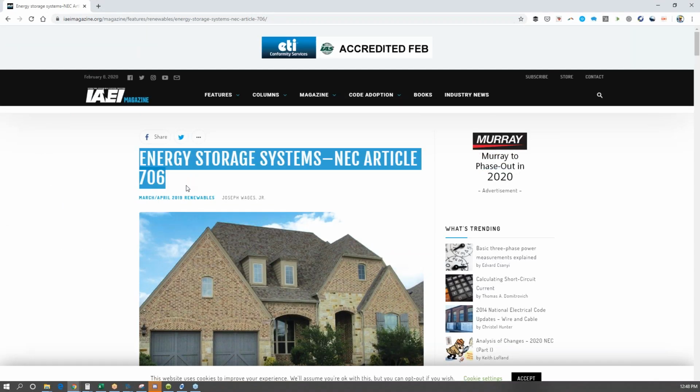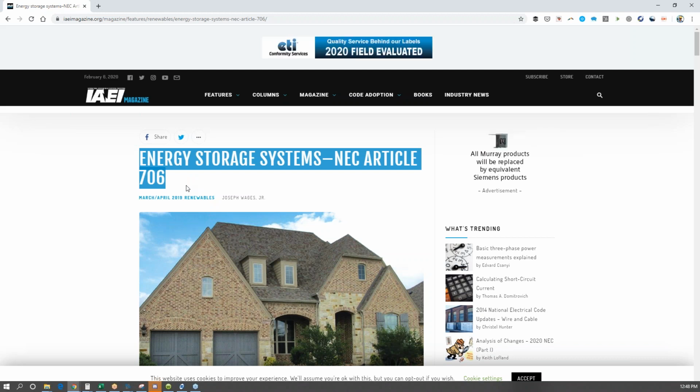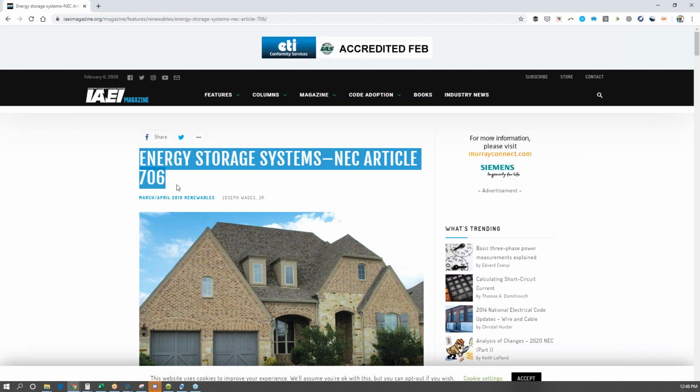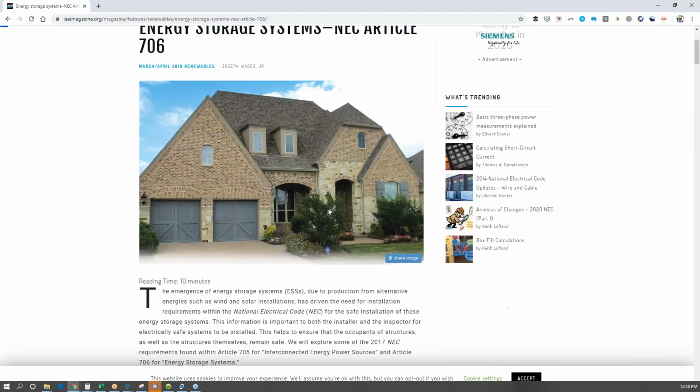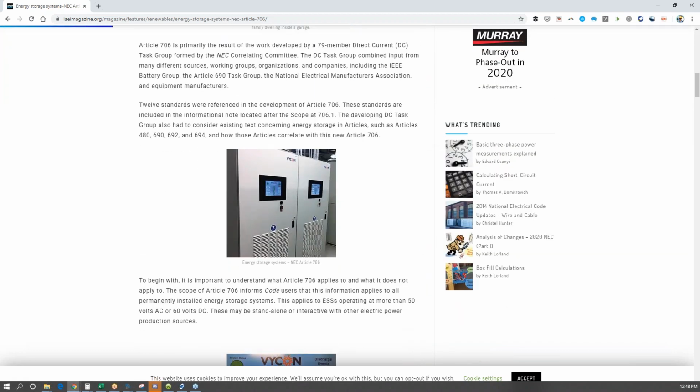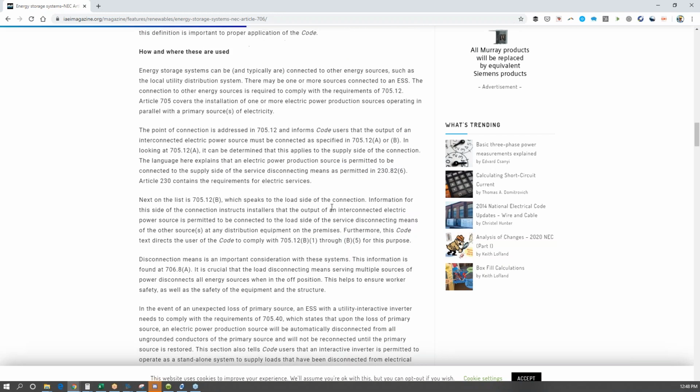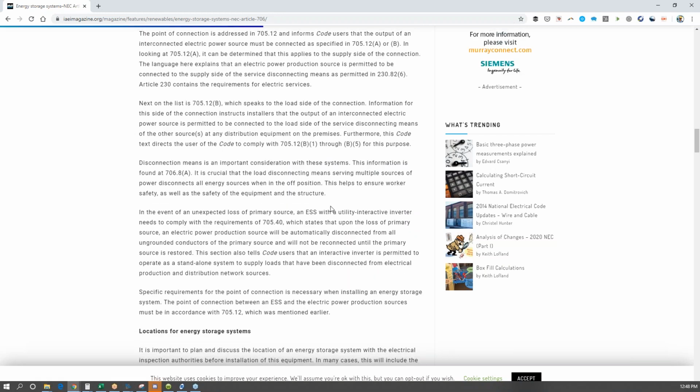There's a whole article of National Electric Code governing energy storage systems that is applicable once your battery bank gets over 600 volts. The big difference between the NEC and the IFC is that the IFC requires continuous venting, whereas the NEC is more just looking to make sure the room has a venting source that can be activated to clear the volume of the room out, or the volume of the container.